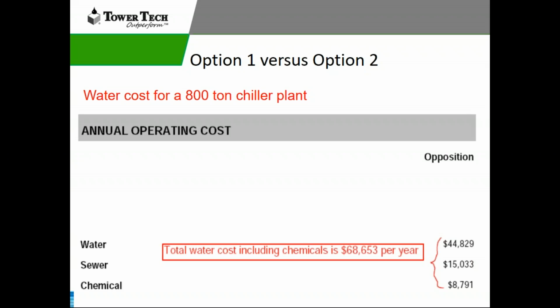In that case, if we're doing a new installation in a new building, air cooled makes a lot of sense, 800 tons and below. When we start getting to that larger tonnage, that's where water cooled really starts taking effect and we get the advantages of the water cooled system above. But from my advantage, what I've seen out here is 800 tons and below, air cooled makes a lot of sense because of the cost of water.